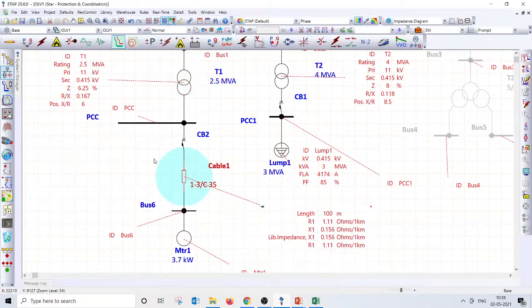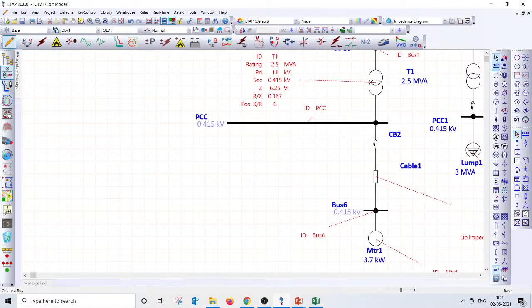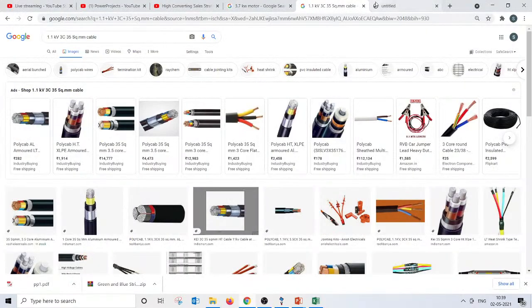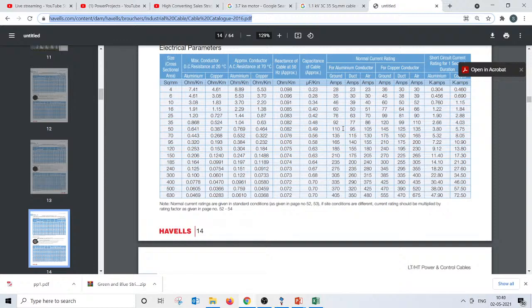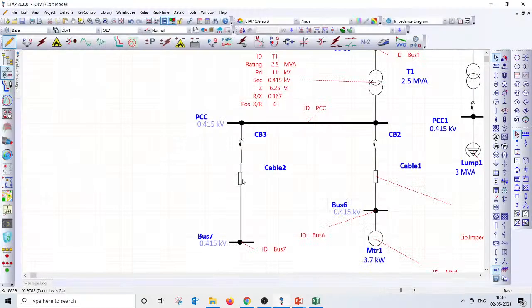For example, if I'm going with a 160 amps feeder, or let's look at something more. Assume that we are going to some MCC, and this MCC has a connected load of maybe 100 amps or something. Then what we need to look at is, to carry this 100 amps, what could be the conductor size we need, correct? Maybe to carry this current you may need a 70 square mm cable. Let's put 70 square mm cable.